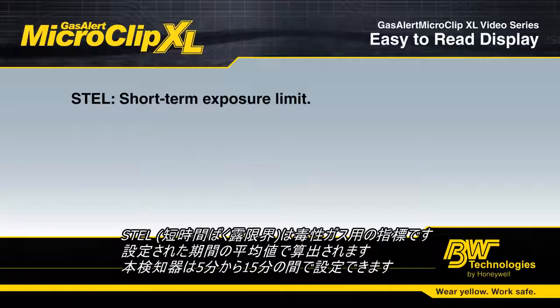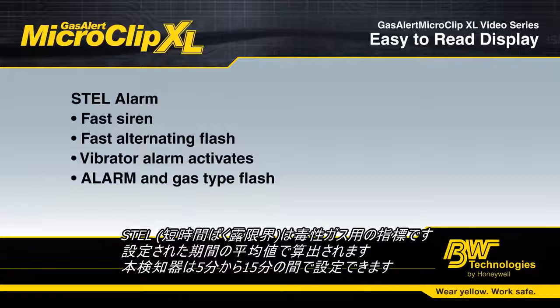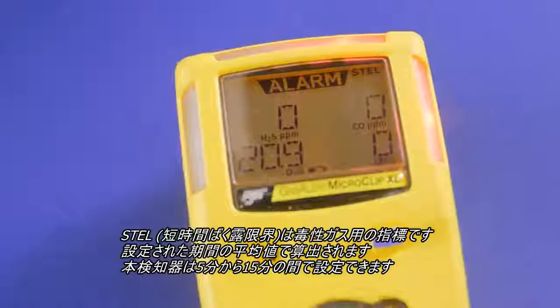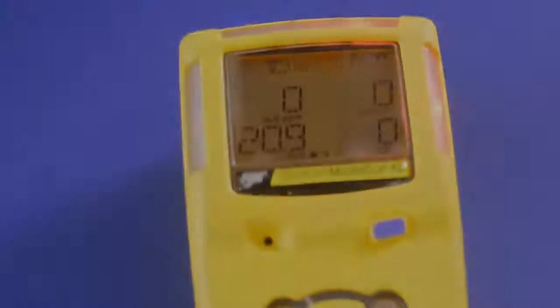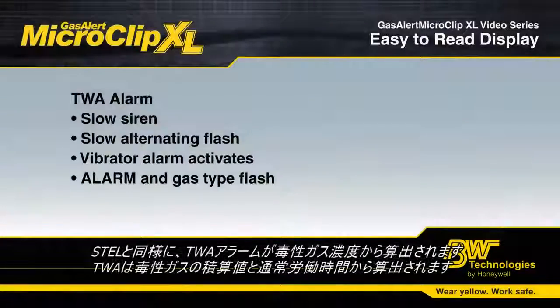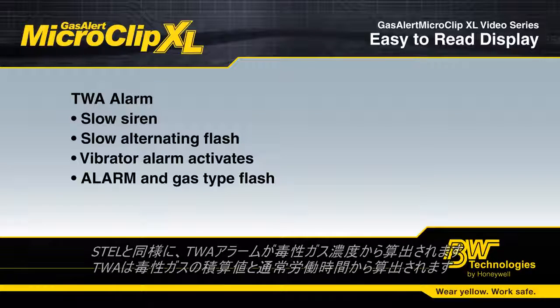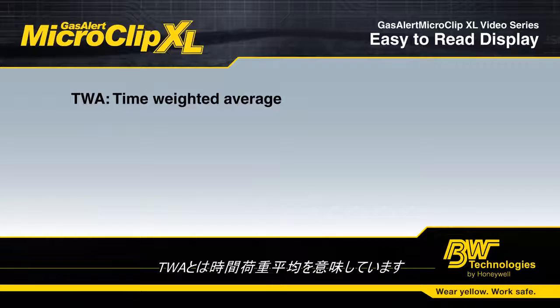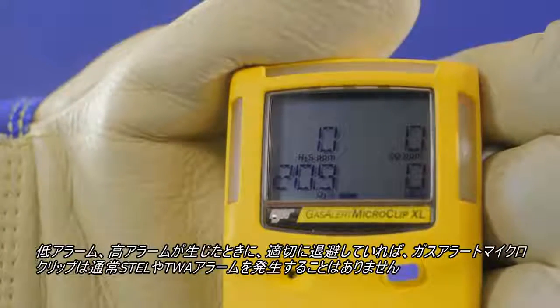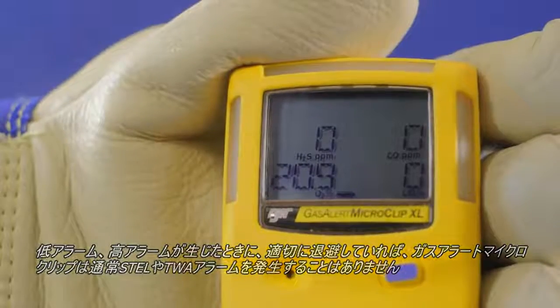STEL readings are calculated only for toxic gases. STEL stands for Short Term Exposure Limit, basically measuring your average exposure over a preset time period. This floating window can be set from 5 to 15 minutes. Like STEL, TWA alarms are also calculated for toxic gases. A TWA alarm signals a cumulative exposure over time, typically an 8-hour period. TWA stands for Time Weighted Average. If you are taking proper action and evacuating any time a low or high alarm is sounded, your GasAlert Micro Clip XL should not go into STEL or TWA alarm.